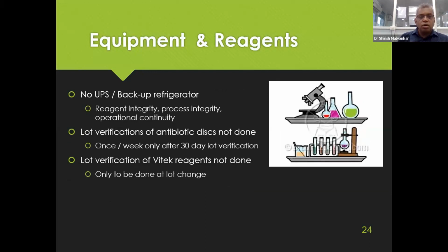No UPS or backup refrigerator. Now, this would put serious questions on the reagent integrity, the process integrity, even on your operational continuity in case of a severe power shortage. In metro cities, I'm sure this is not much of a problem. But in the smaller cities, in the smaller towns, where power is a problem, you need to have all your equipment on appropriate UPS in order to maintain reagent integrity.